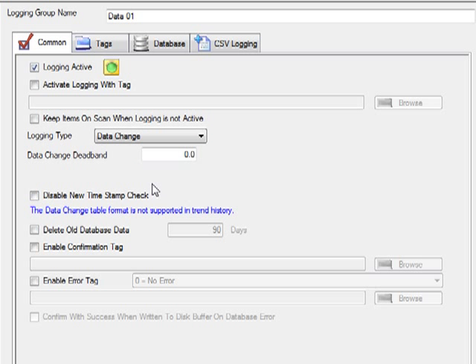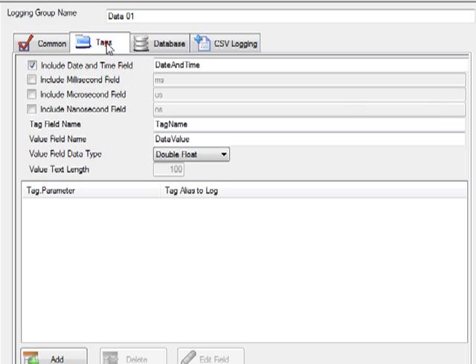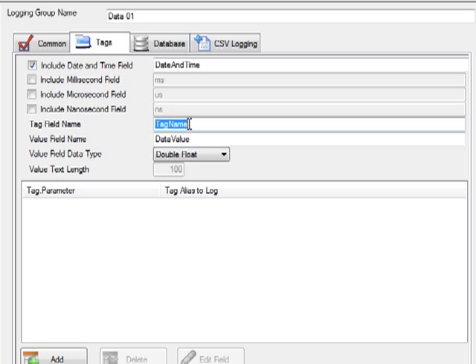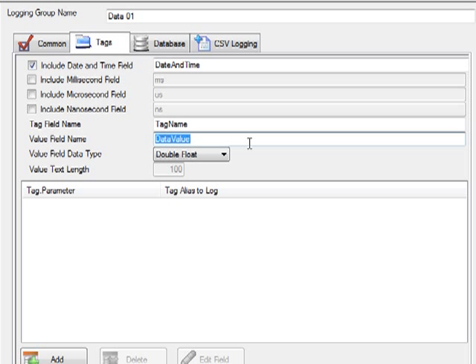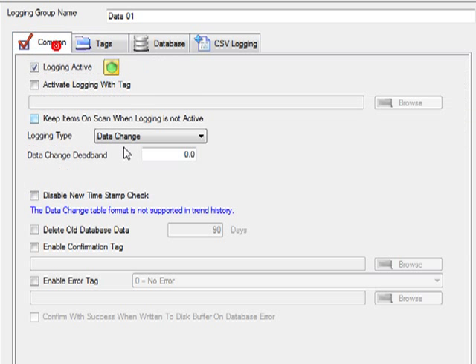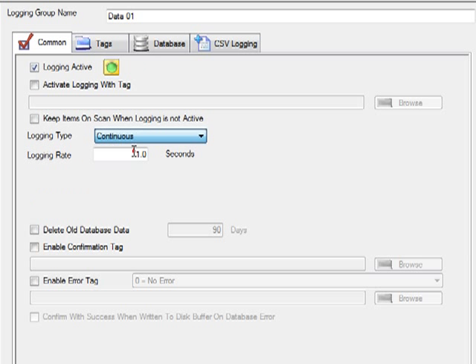The DataChangeType is a narrow format where it only defines three specific fields to log to: the date and time of the value, the tag name which can be an alias name for that particular point, and the value field. So with this type, you can set it up to log a million values all in one table, but it is a little bit more difficult to get the information out because you have to query it by a specific tag name field.